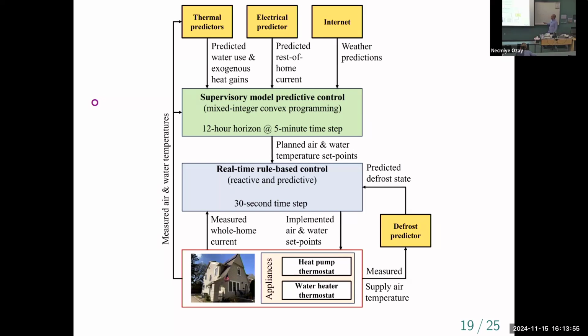And then we added another layer in our control hierarchy. So we still down here have the manufacturer controls. We still have our supervisory control layer. But now we added an intermediate control layer, which just does sort of rule-based control logic, if-then type logic. And that basically was an added layer that we found was necessary for robustness.